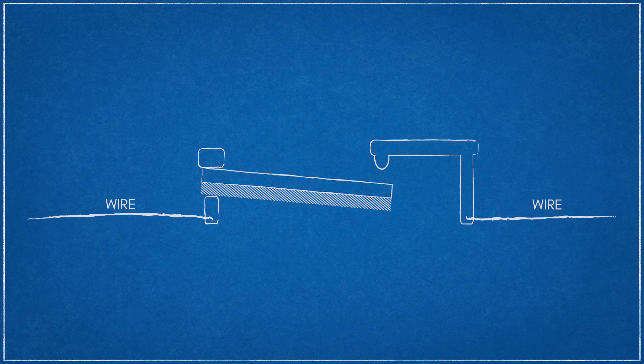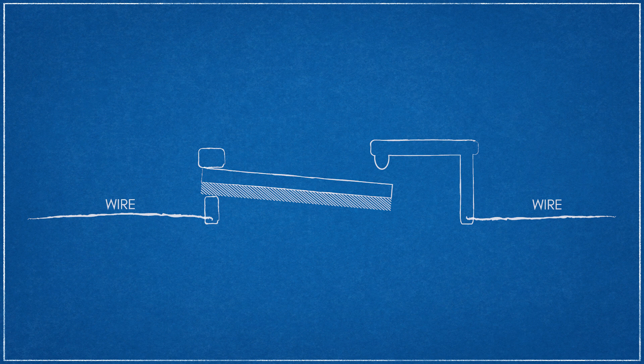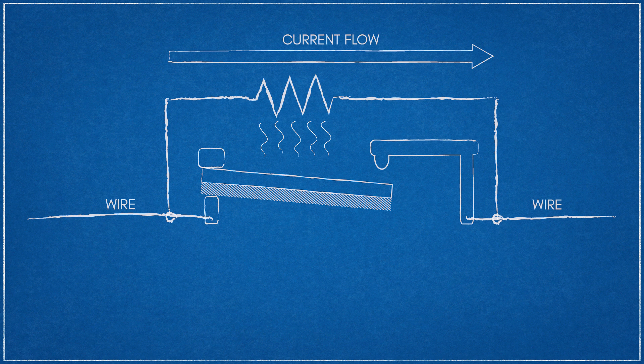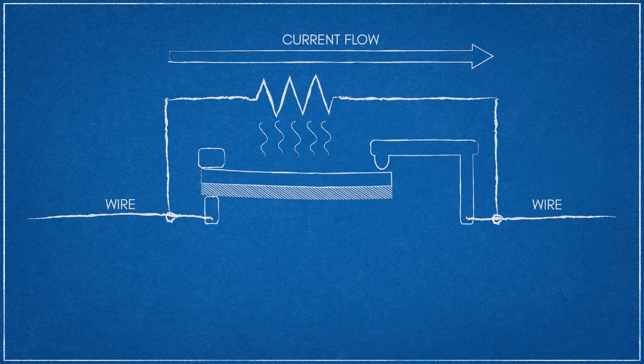We can expand on the functionality of bimetallic switches further by mounting an electrically resistant heating element to the bimetallic strip. As current flows through the heating element, the electrical resistance causes a dissipation of heat, raising the temperature of the bimetallic strip. As it heats up, the thermal motion causes the bimetallic element to switch on the flow of electricity.